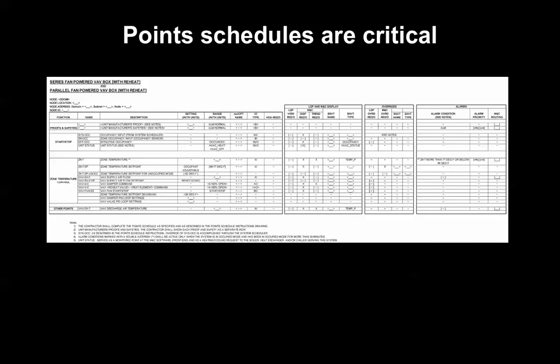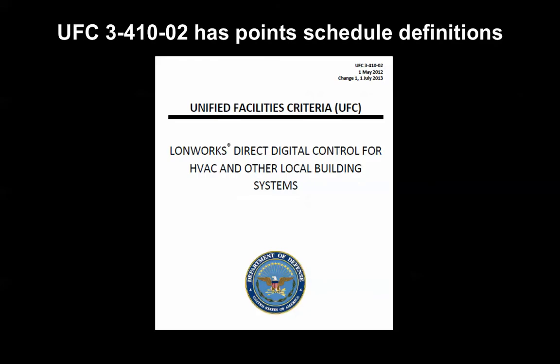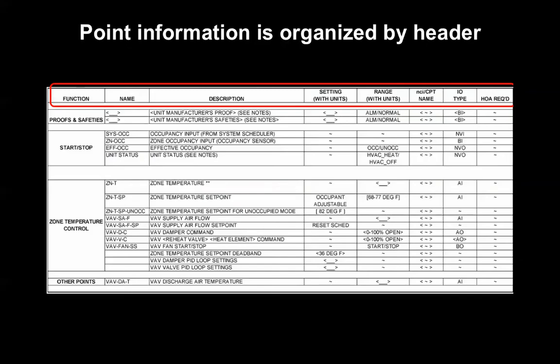But really the most critical thing that we could talk about as far as these design drawings are going to be the point schedules. So there's a lot in these point schedules and it can be a lot to take in at first. So we're going to kind of break this up and look at some of the different columns, how they're used and why they're important. For right now we're going to focus on the left half of these because we can really break down different operating parameters with different front end type use points and how they're used. So if you look at our unified facility criteria, we have different definitions for all of these elements inside the point schedules and we're going to use those to go through some of these. The UFC starts by talking about what the point schedule is, what it's used for and who's responsible for filling out different ends of it, as well as all these different headers. So we're going to go over some of those definitions here.